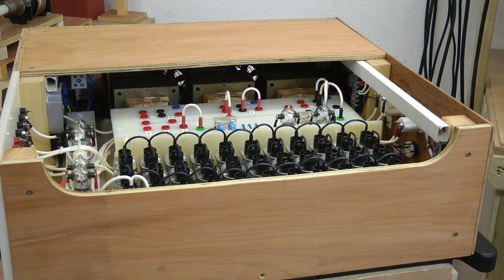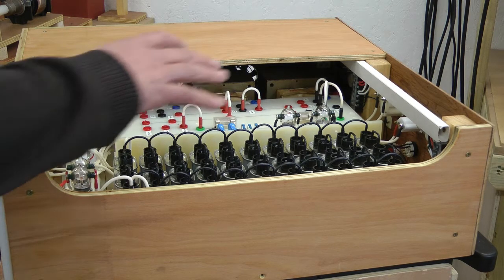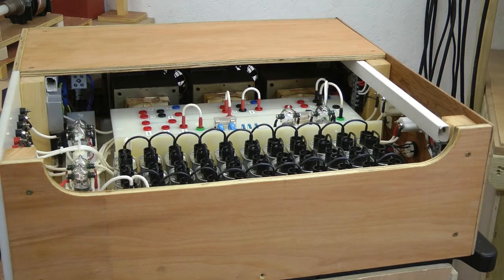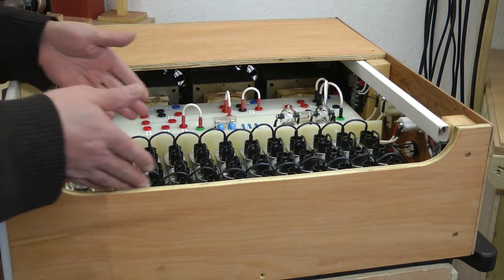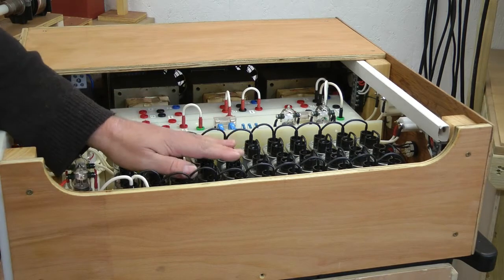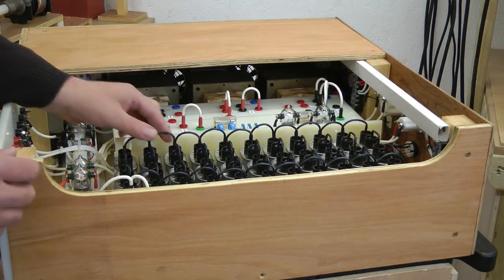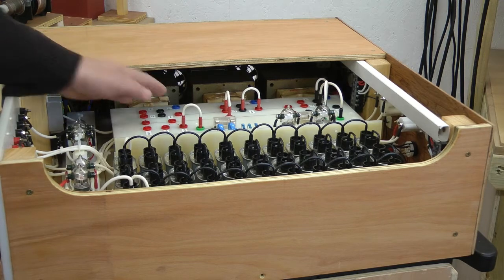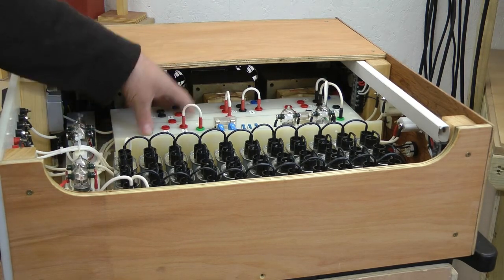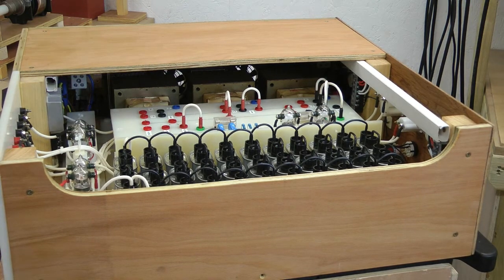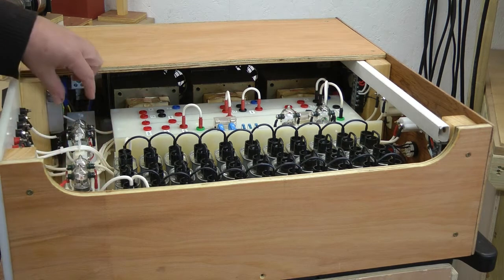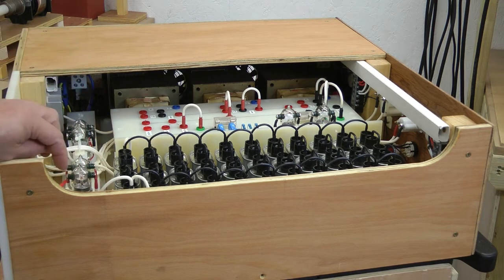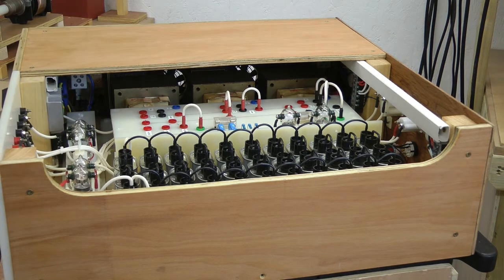So what I'm going to do is take out. This is designed in a modular way. So in other words, this section, which consists of the level shifter and the monitoring circuit, comes out as one board, and the transformers, the bridge rectifier and the patch board also come out as one unit, and so does the high voltage discharge unit. They are all removable units from this, and then that allows us to see.